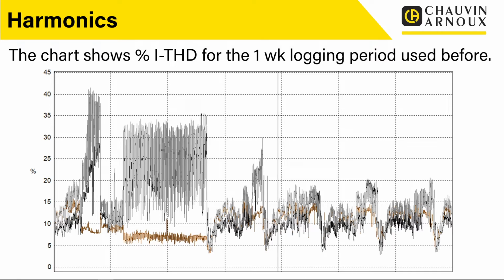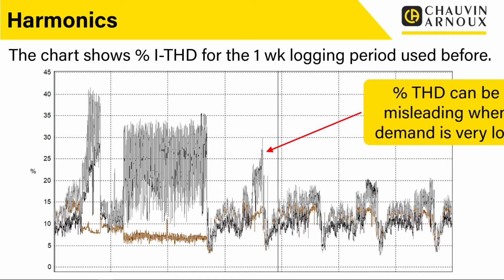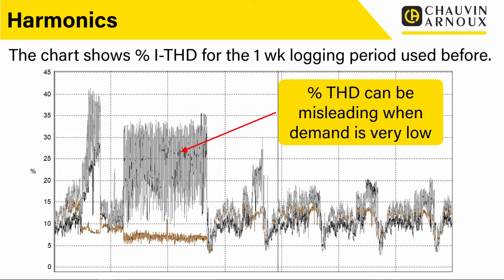But there is actually this confusing bit here, which looks like it's got very high harmonics, this period here. And this is where percentage THD can actually be a little bit misleading because it's a percentage. So there's a couple of things going on here. Obviously, this period was over the weekend, so there wasn't a lot of current demand going on. But because we're measuring it as a percentage, the actual harmonics seem bigger because they're a greater percentage of that low current demand. So always be careful when you're measuring percentage THD that if you have got low loads, the distortion can seem higher as a percentage.